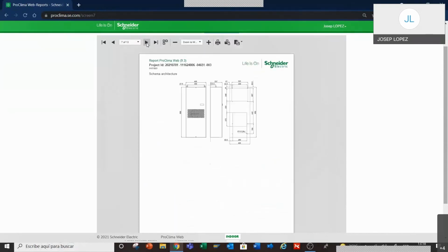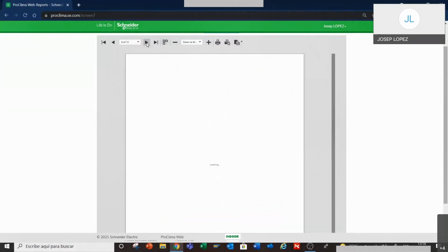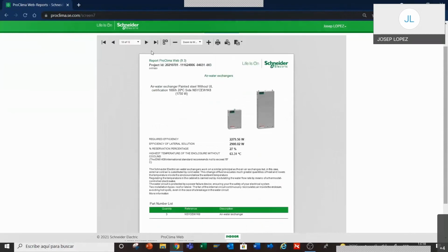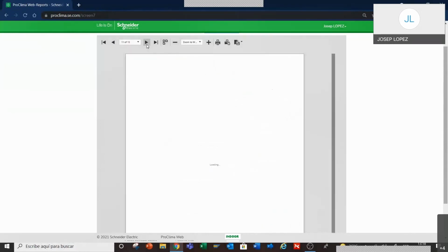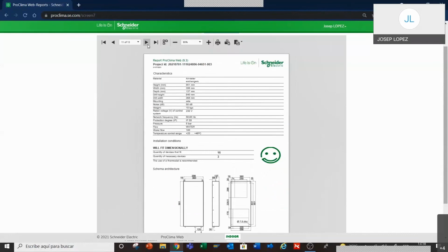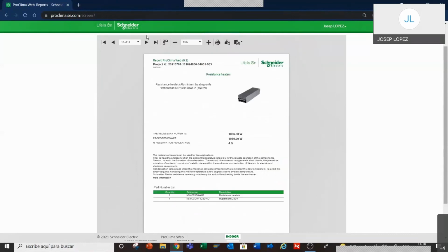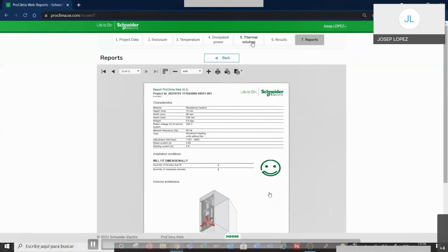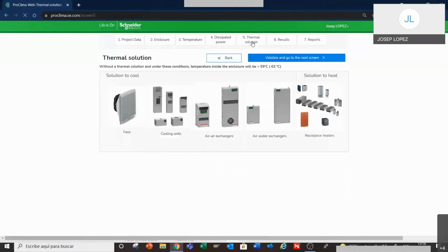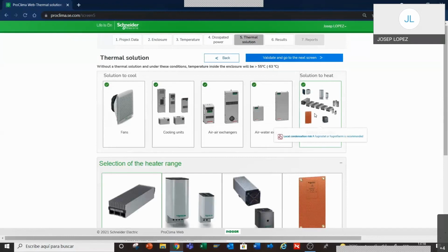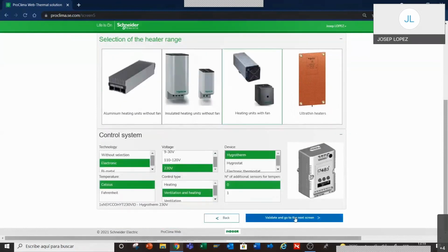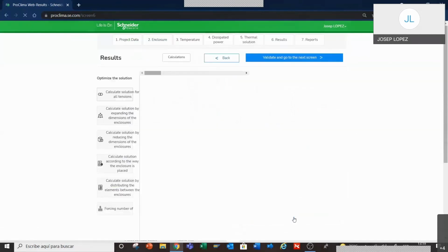So it allows you to show the facility manager or the end user different options, and according to that, it is easier to take a final decision in terms of complexity of installation or, for sure, budget. Okay, and let me come back because I would like to show you some insights. Here you see that the software indicates the pain points, the problematics with these 4 heaters. And now we are going to reduce these 7 heaters to 3, okay?